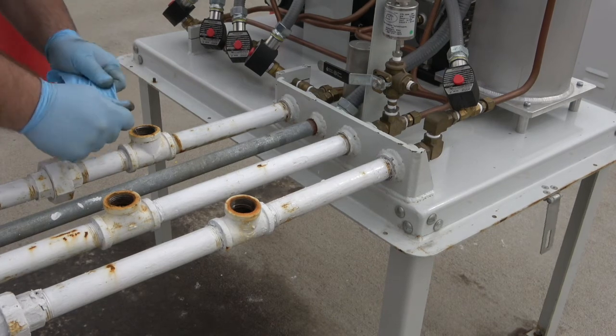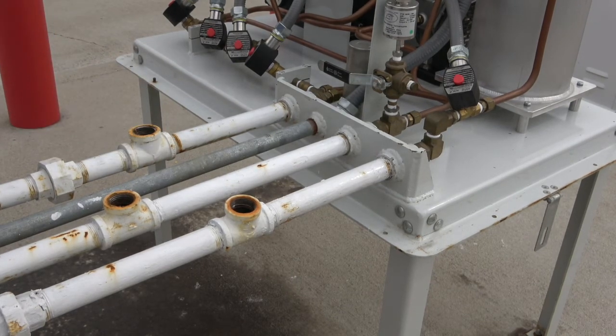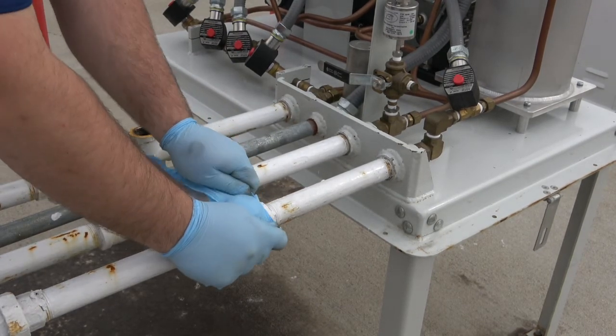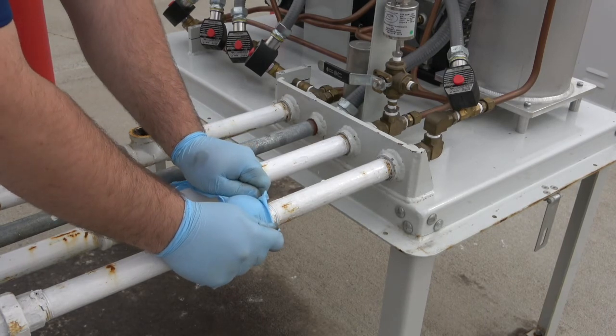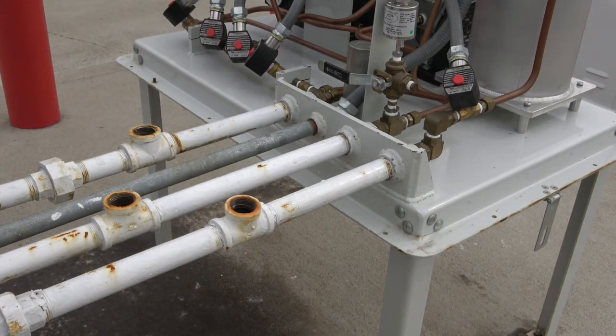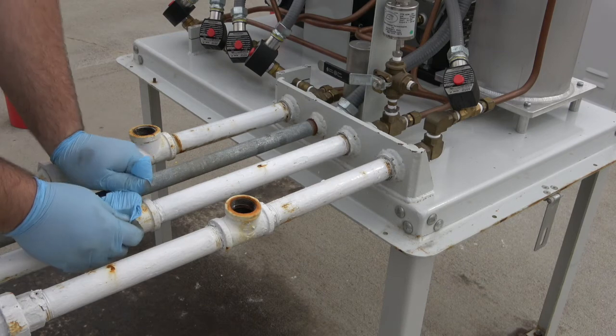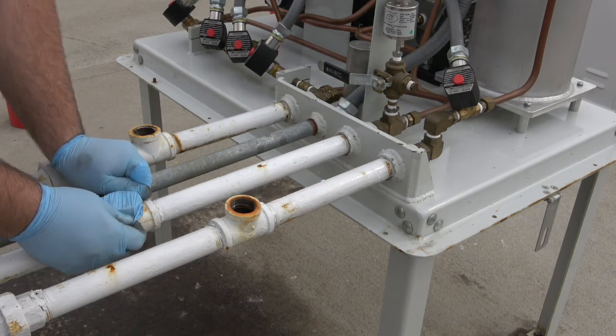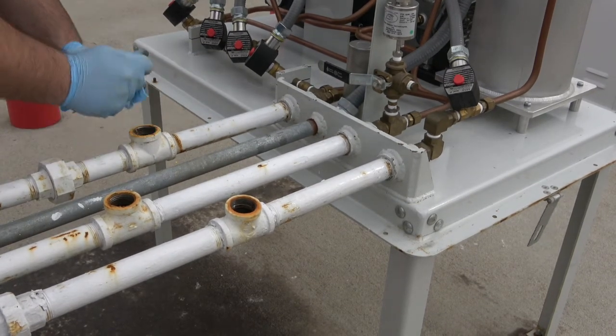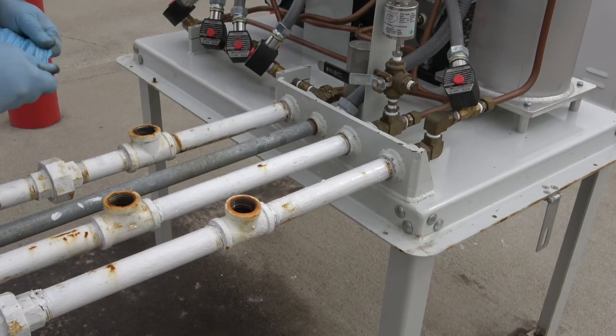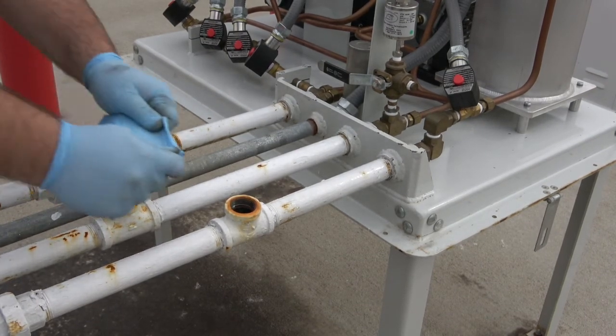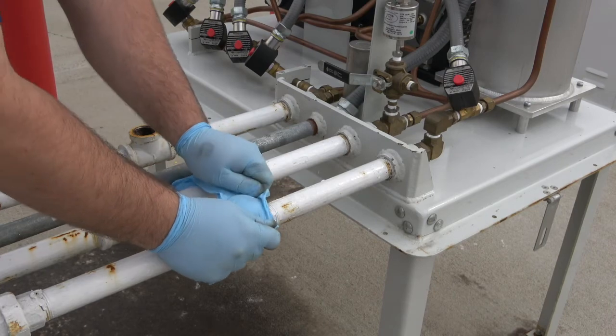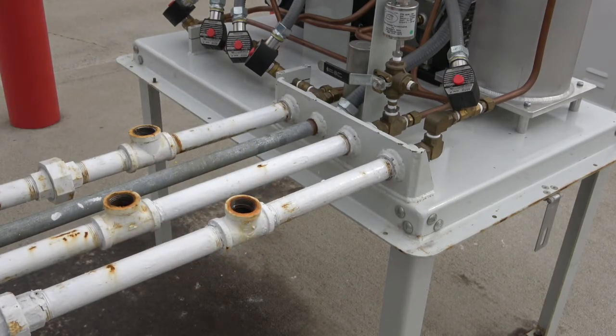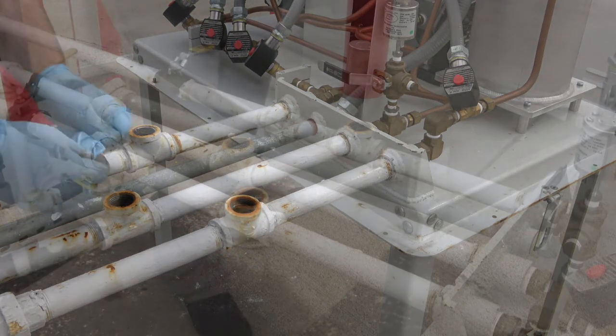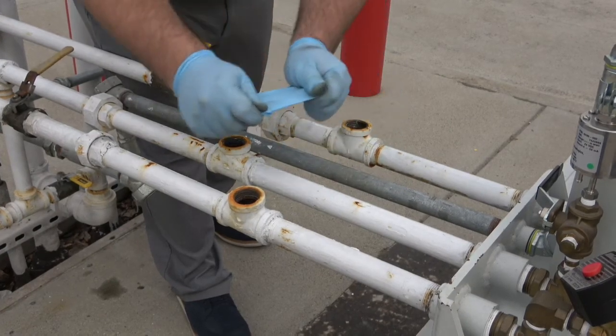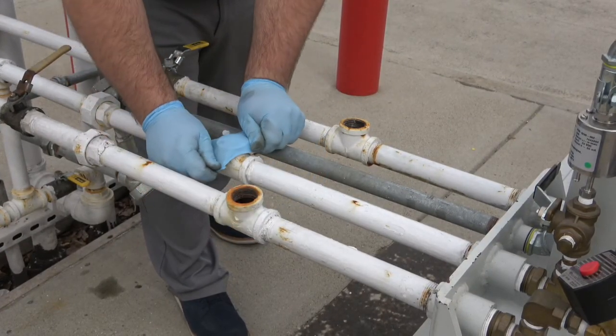During the run mode, place your hand over each open T-fitting. You should feel the following: suction at the vapor inlet T, air blowing from the air outlet, and no blowing or suction from the vapor return. If there is suction or air blowing from anywhere unexpected, refer to the troubleshooting section of the Green Machine manual in Chapter 8.